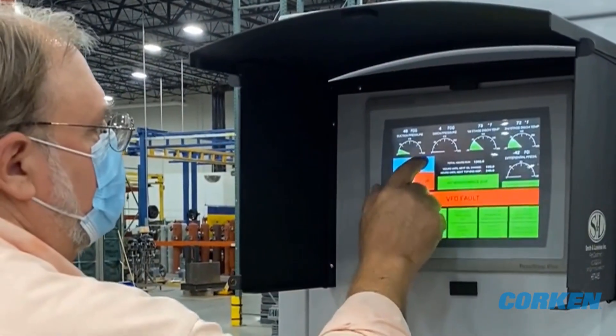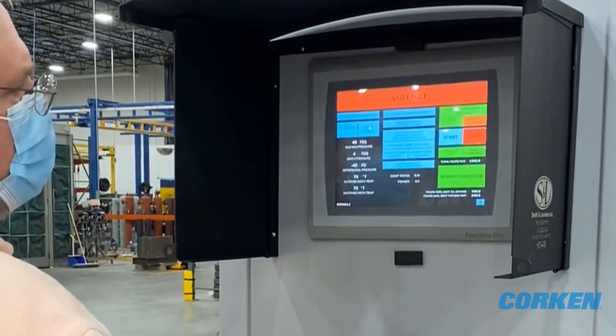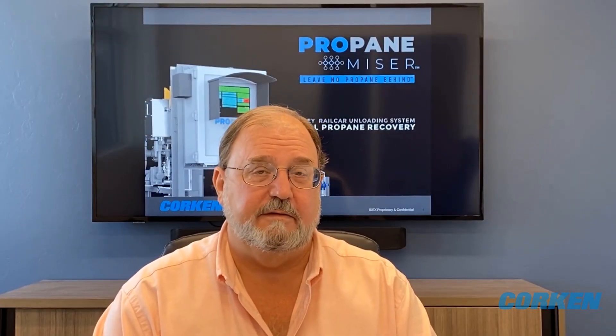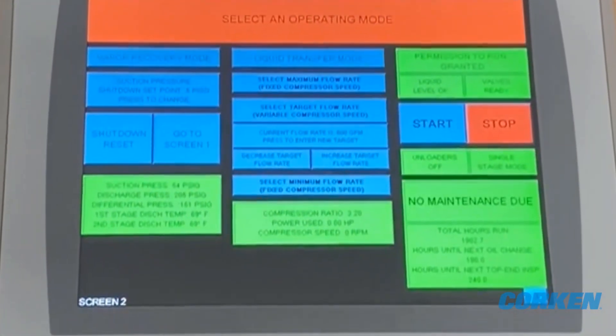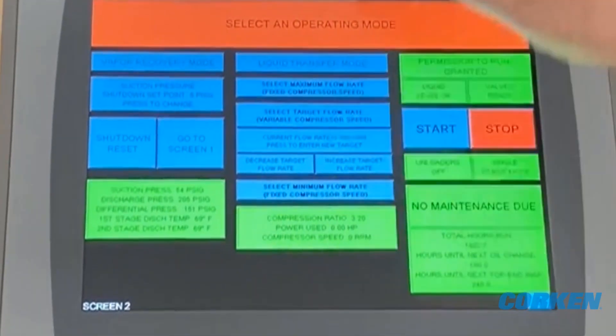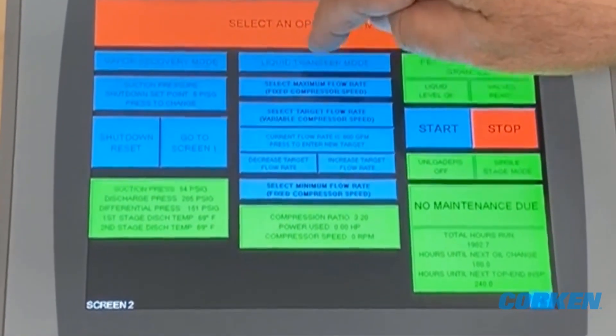Previous designs might give the operator access to two or three speeds. PLCs and VFDs have improved enough to give us access to the compressor's minimum speed, its maximum speed, and all speeds in between. We also have enough computing power to run the algorithm that allows the operator to choose the optimum flow rate for the operation. The touch screen allows us to make a user interface that is both intuitive and easy to use.